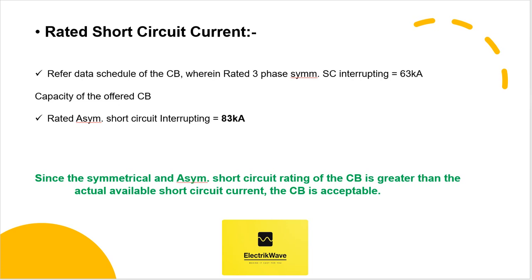Checking as per the data schedule of the circuit breaker, the rated three-phase symmetrical short circuit interrupting capacity of the offered 400 kV circuit breaker is equal to 63 kA, and the rated asymmetrical short circuit interrupting capacity is equal to 83 kA. Since the symmetrical and asymmetrical short circuit rating of the circuit breaker is greater than the actual available short circuit current, the circuit breaker is acceptable.